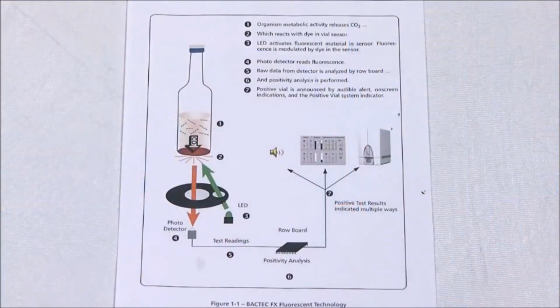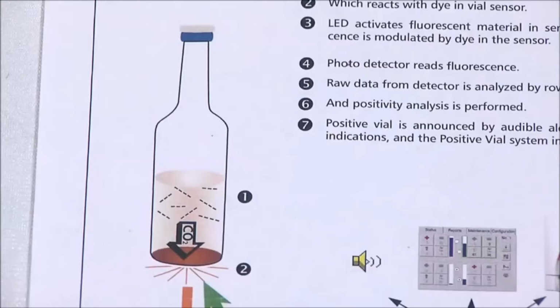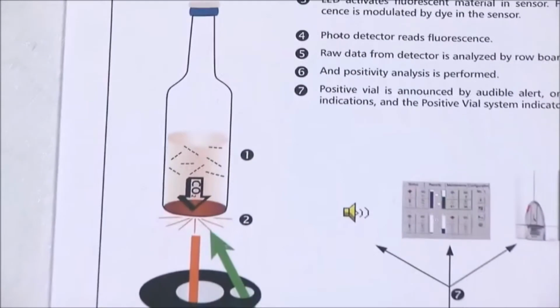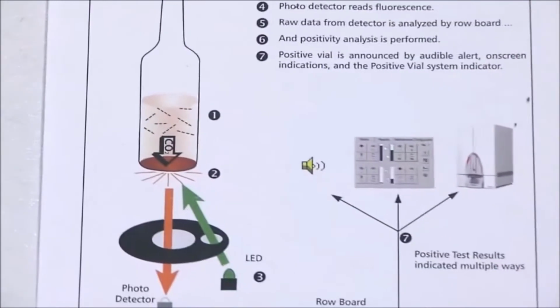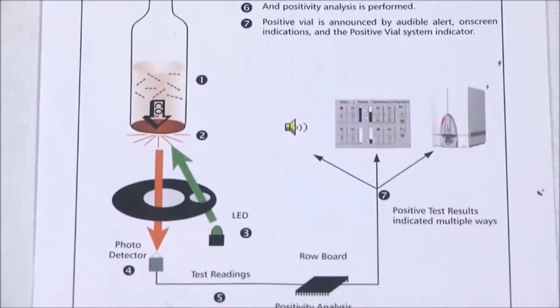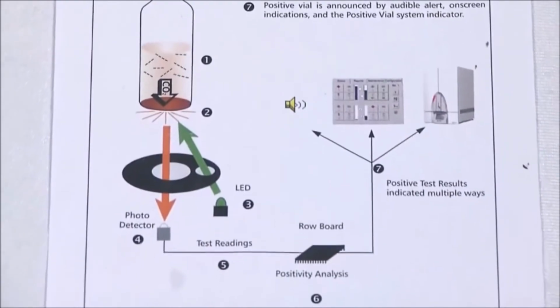When microorganisms are present in the blood culture, they metabolize the nutrients within the culture medium and release carbon dioxide into the medium. A dye sensor in the bottom of the vial reacts with the carbon dioxide. This reaction modulates the amount of light absorbed by a fluorescent material in the sensor. Each blood culture station in the analyzer contains a light-emitting diode photodetector, which measures the level of fluorescence every 10 minutes.